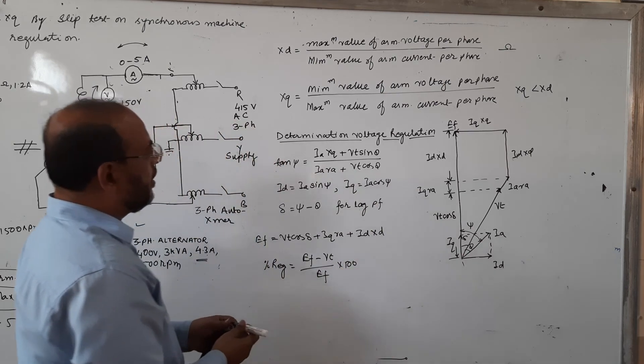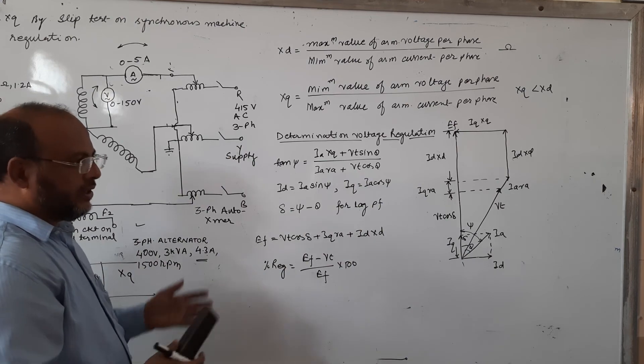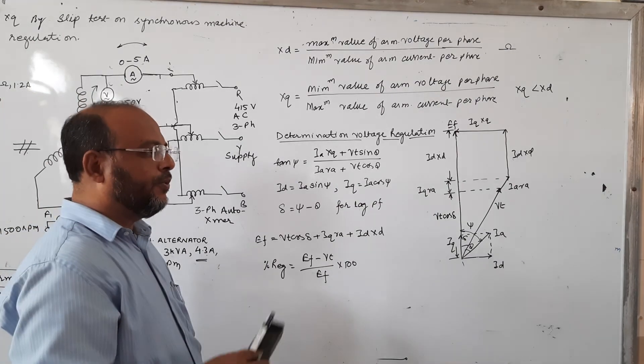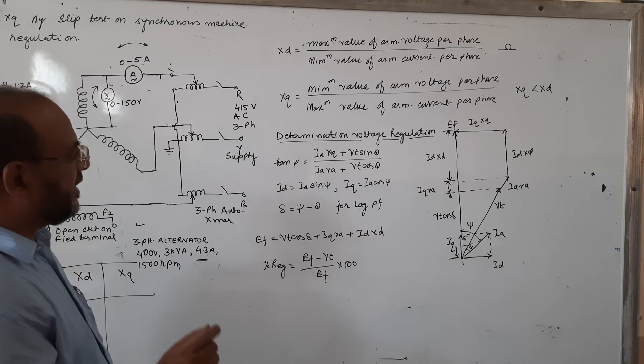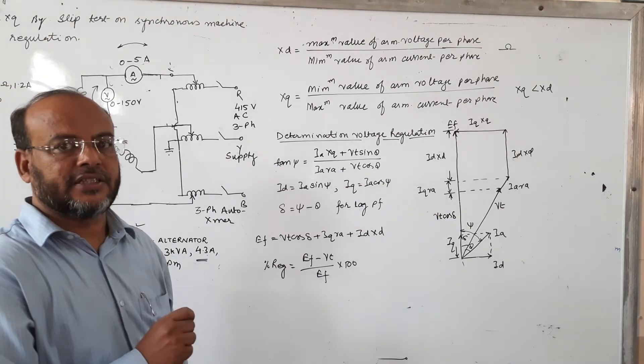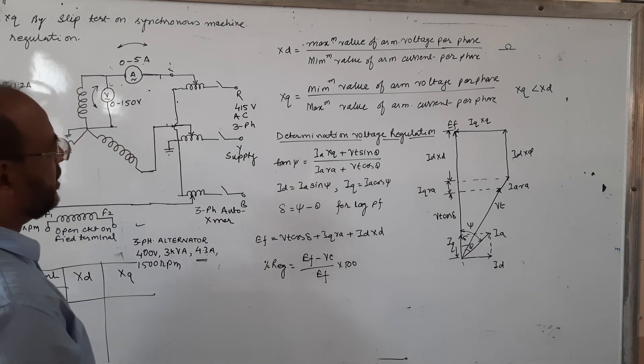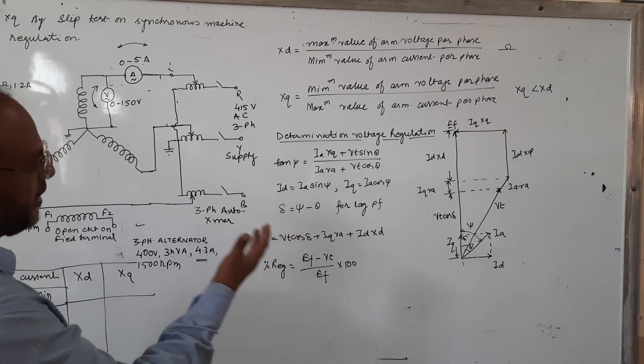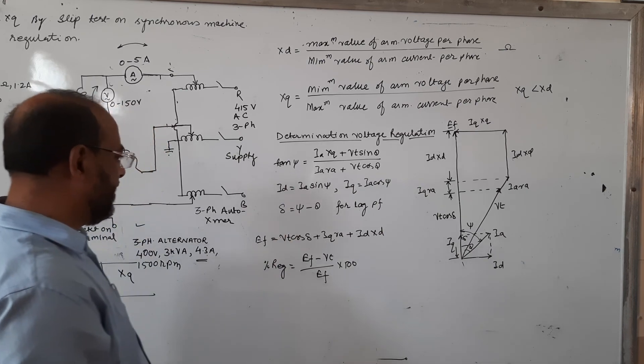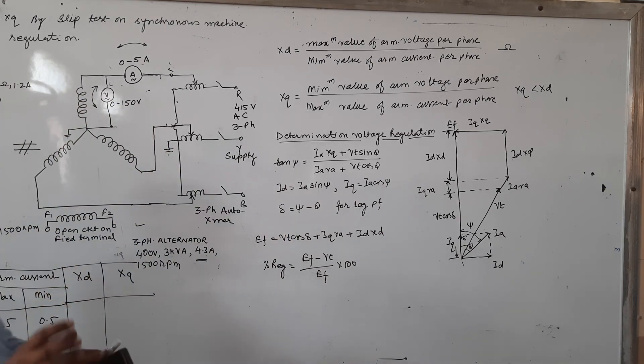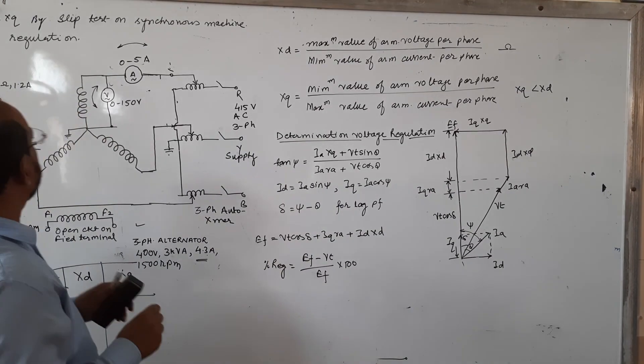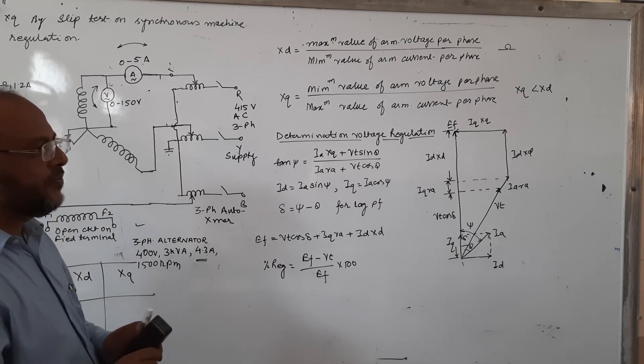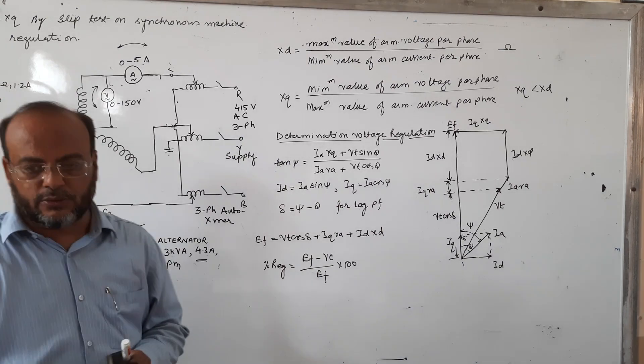By this method, the determination of voltage regulation of a salient pole synchronous alternator can be found. Note that the voltage regulation of a salient pole synchronous alternator cannot be determined by the EMF method, MMF method, or ZPF method. The correct way is to first find Xd and Xq by the slip test, then draw the vector diagram using these values to estimate the excitation voltage Ef, and finally calculate the voltage regulation.